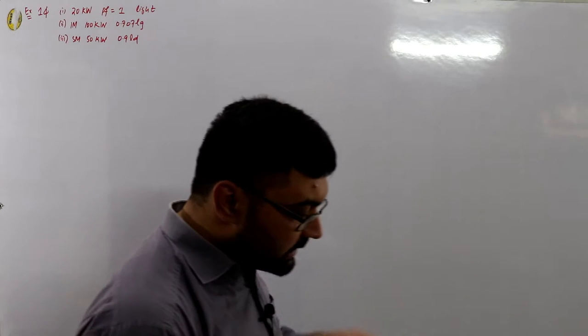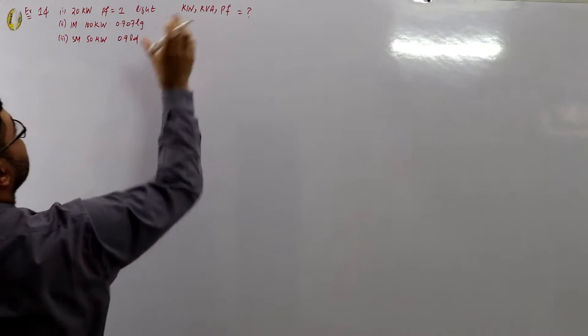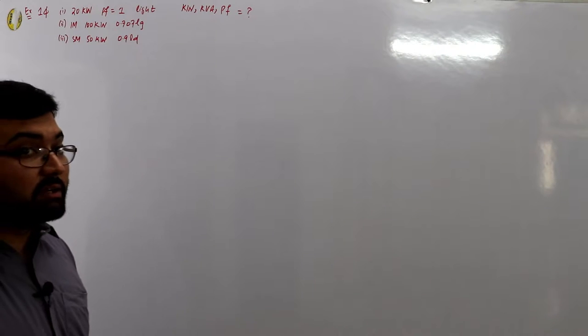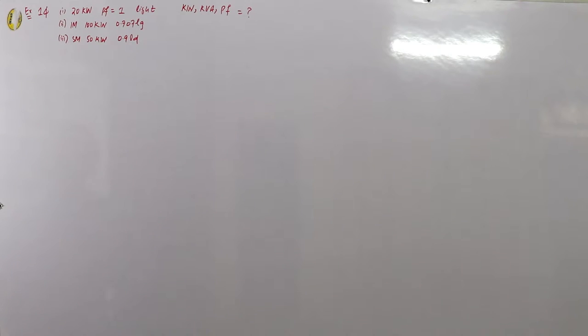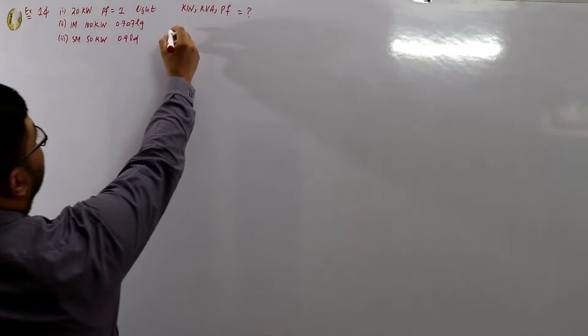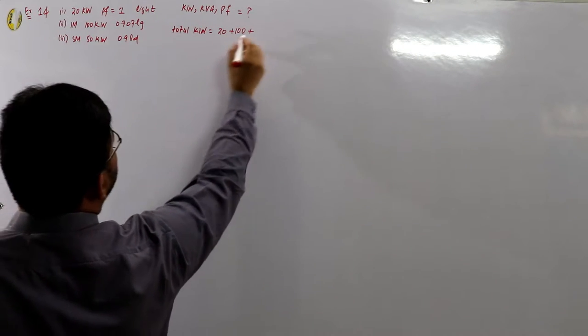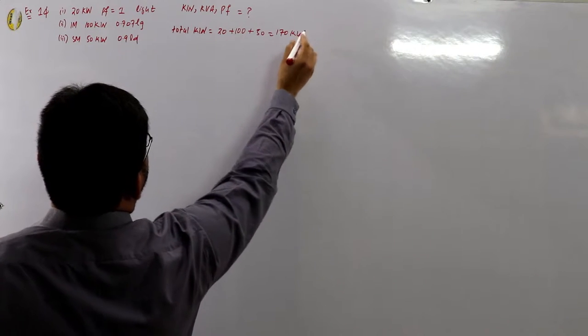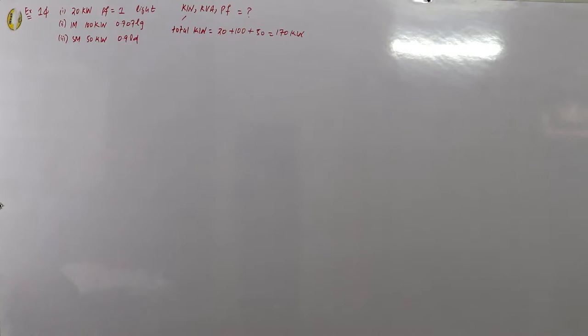Calculate the total KVA and kilowatts delivered by the generator and the power factor at which it works. The total kilowatts, total KVAs, and the power factor of the generator are all unknown. The total kilowatts can be found directly: 20 plus 100 plus 50 equals 170 kilowatts delivered by the generator.